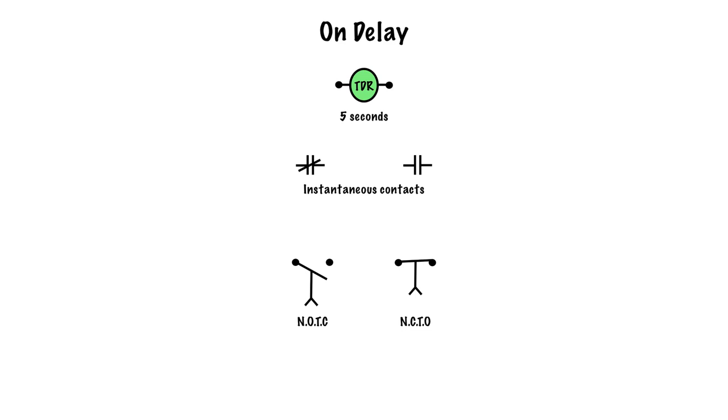What happens though is this coil is energized, but this normally open time to close stays open, and this normally closed time to open stays closed. They hold in those positions until the relay times out. So it counts to 5: 1, 2, 3, 4, 5, and then this will close and this will open. After 5 seconds, this becomes closed, this becomes open.